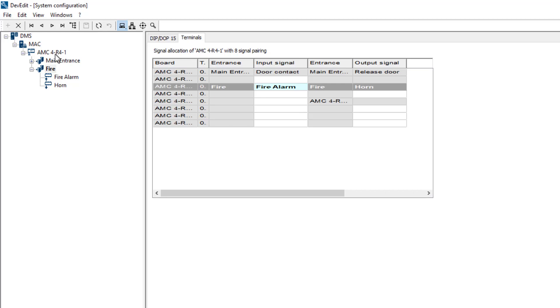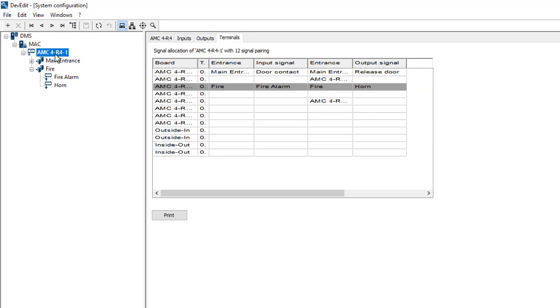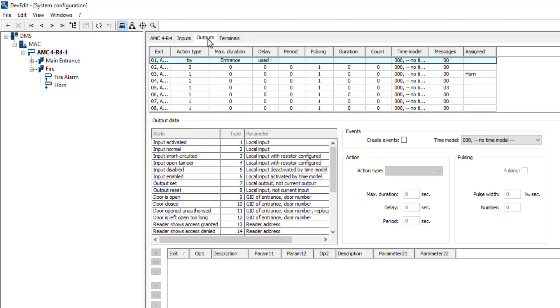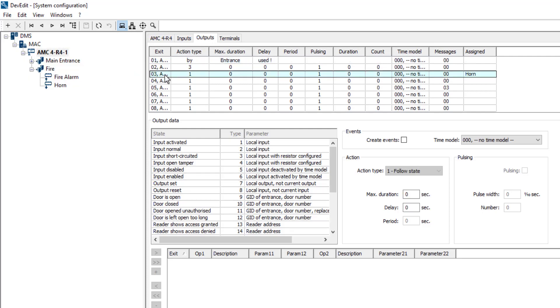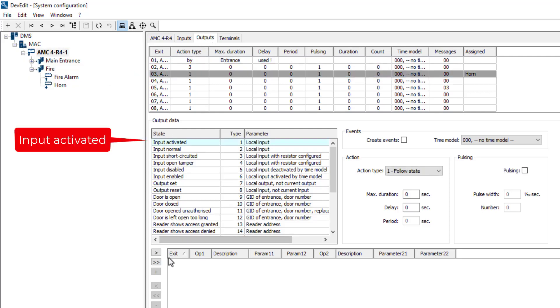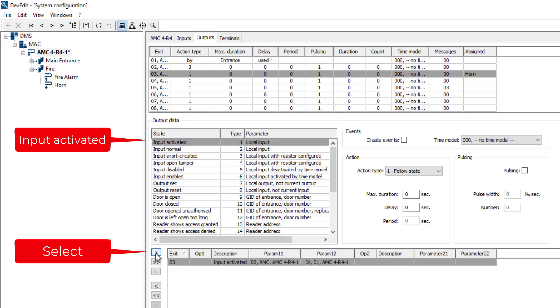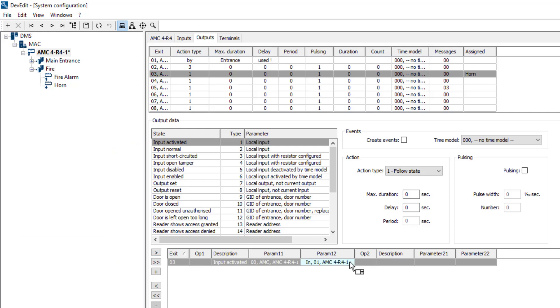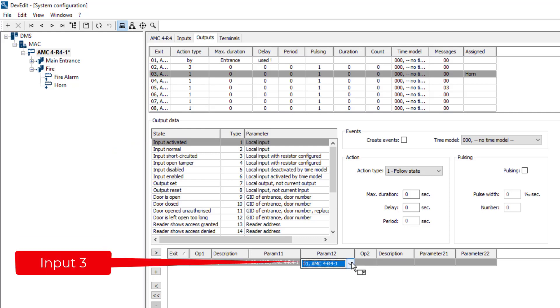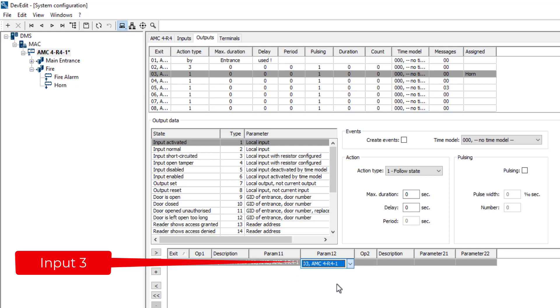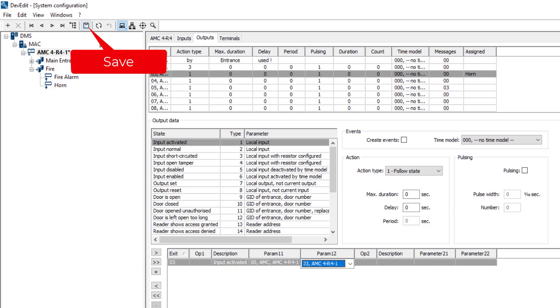Now we move back to the AMC so that we can configure the DOP to follow the DIP. From the outputs we select number 3, the horn. Then we select input activated as state. Now we choose input 3, the fire alarm. The AMC recognizes the new state of the input, fire alarm activated, and will send a signal to the output. Start making noise. Next thing to do is connect the wires.